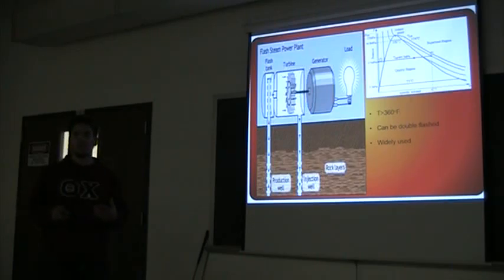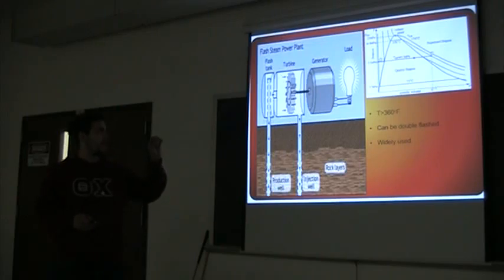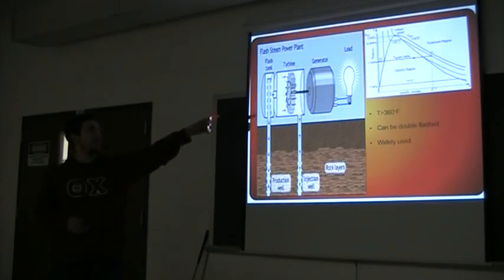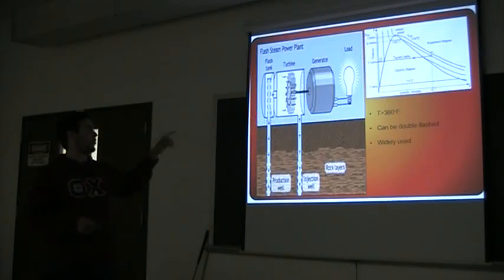To solve this problem, the most commonly used type right now is the flash steam power plant, where you don't have temperatures that go into the superheated region but they are still high enough that you can create a change of volume to take it to that final superheated stage needed to enter the turbine. You can flash it more than once to get more power out of the process, and this is the most commonly used right now.